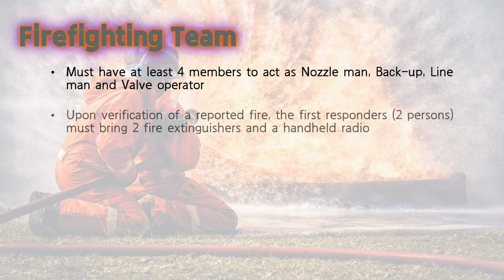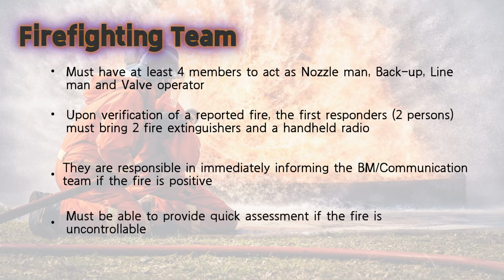Firefighting team. Must have at least 4 members to act as nozzle man, backup, lineman and valve operator upon verification of a reported fire. The first 2 responders must bring 2 fire extinguishers and a handheld radio. They are responsible for immediately informing the brigade marshal or communication team if the fire is positive. Must be able to provide quick assessment if the fire is uncontrollable.